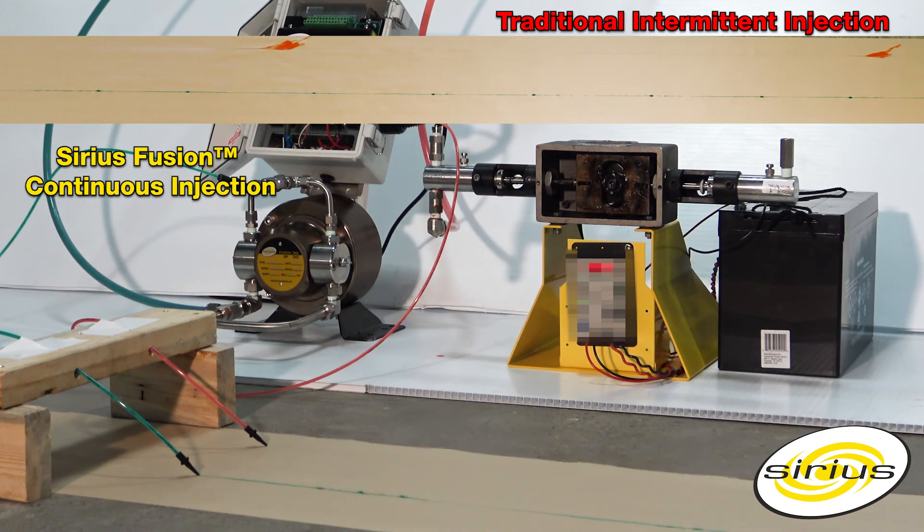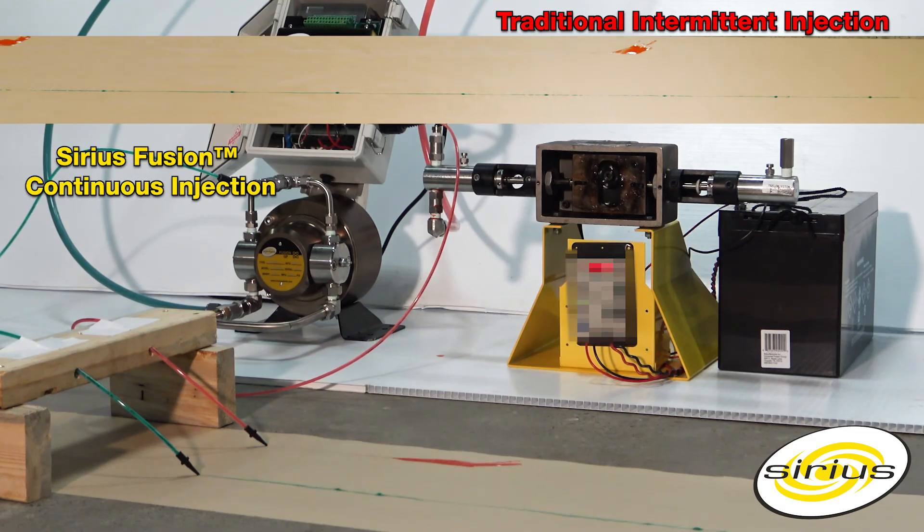This uniform and continuous flow ensures that the chemical has the best opportunity to disperse both radially and axially in the flow stream. Radially meaning across the pipe and axially meaning up and down the flow stream. Axial dispersion cannot be achieved using intermittent flow.